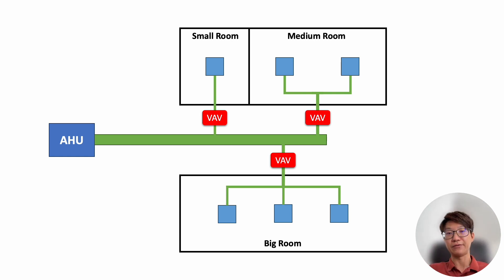So here our case is we have three VAV. So the VAV is actually handling the total airflow in each of the rooms. Then the diffuser will separate the airflow later on. Then the second component we need is the thermostat. We need one thermostat in each of the rooms. So each of the thermostats is corresponding back to their VAV box. And the third component we need is a VSD to the AHU. Basically we are upgrading the AHU because traditional AHU is fixed speed. They can only run in one fan speed. So producing one CFM, producing a certain CFM only. Now with a variable speed drive, we can change the hertz, the frequency of the power. Maybe 50 hertz, 60 hertz, down to 40 hertz, 30 hertz. This will change the fan speed. Then you change the airflow. And the final component we need is a DPS, a duct type DPS inserted into the duct to sense the pressure inside the duct.